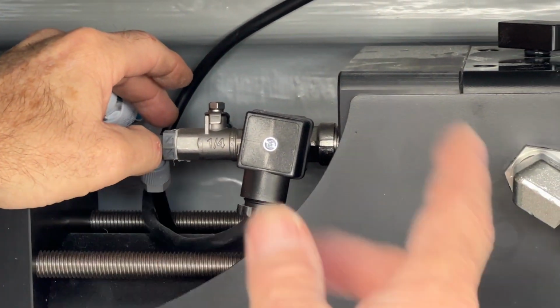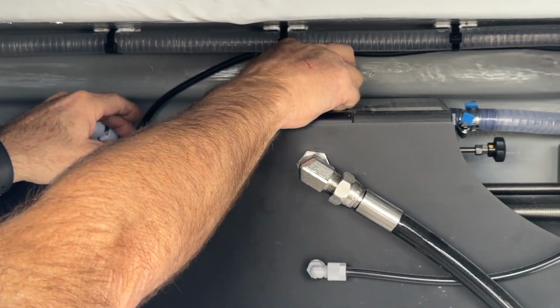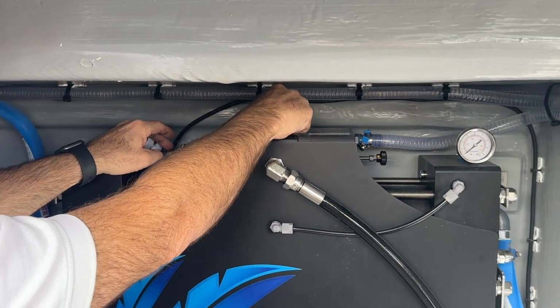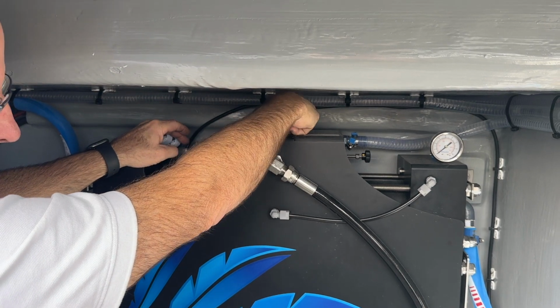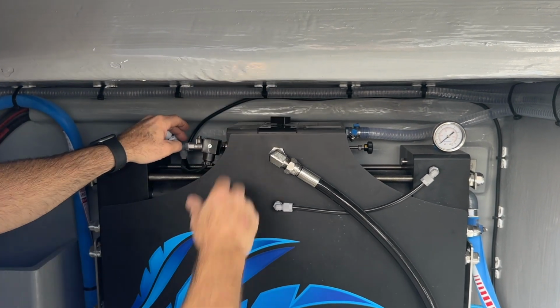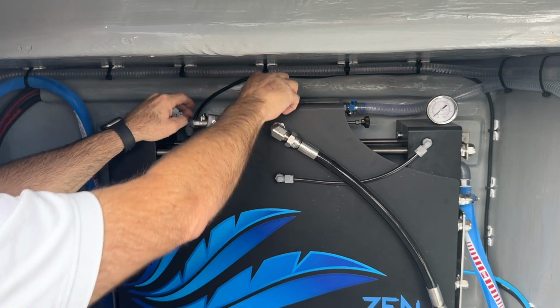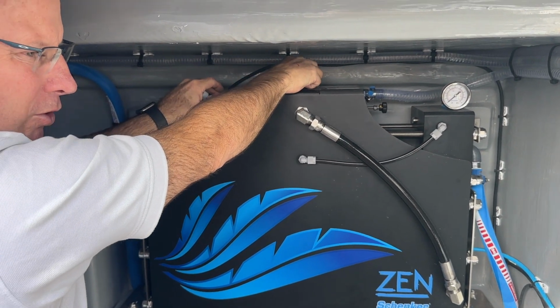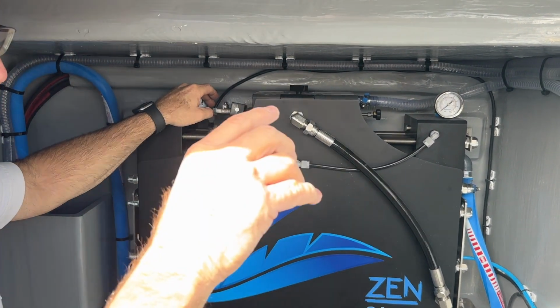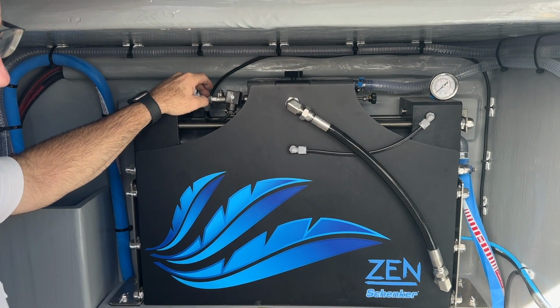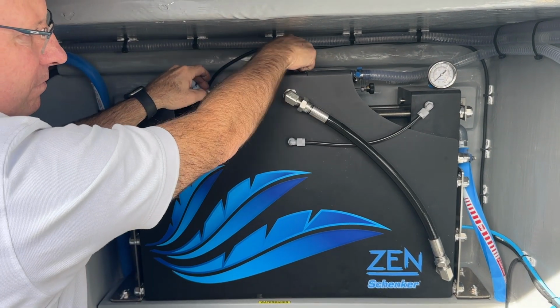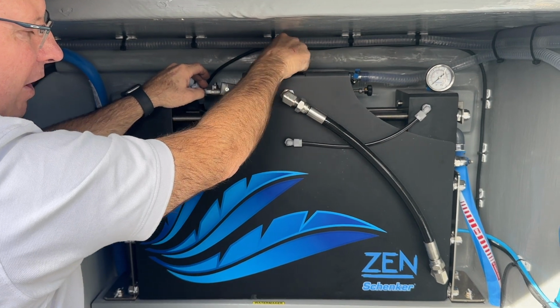Then you go and start the unit and come back here, and once you've expelled all the air out, you can then close the decompression valve. So that typically is just a half a turn. If it's a full turn for too long, the system won't see the correct pressure and will keep turning itself off. Okay. And just hand tight.